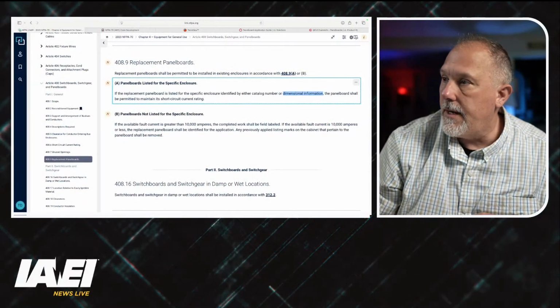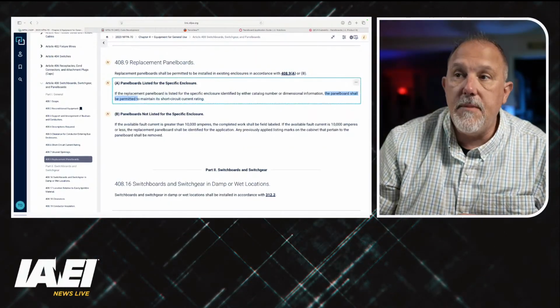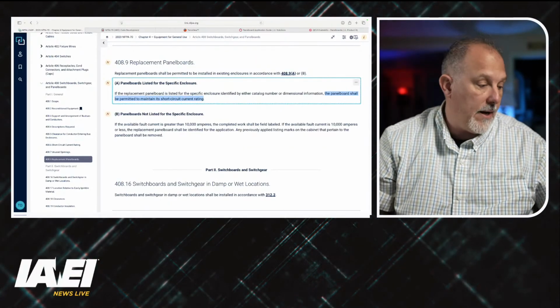And what it says is the panel board is permitted to maintain its short circuit current rating. So if I have a retrofit interior that is designed for a 24 by 4 by 36 box, and I go to manufacturer Schmuckatelli, and I take his interiors out, and I measure the box, 24 by 36 by 4, whatever, and my panel board is designed for that size of an enclosure, I'm in 408.9A.